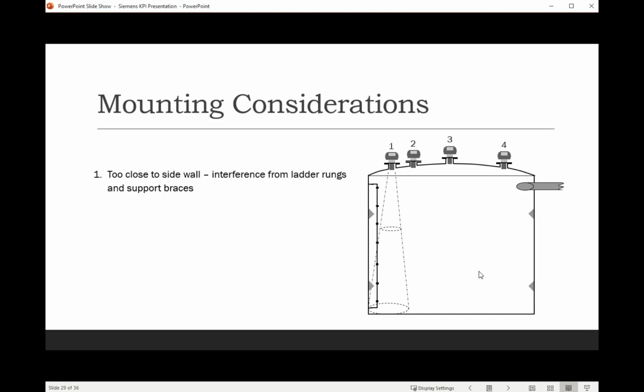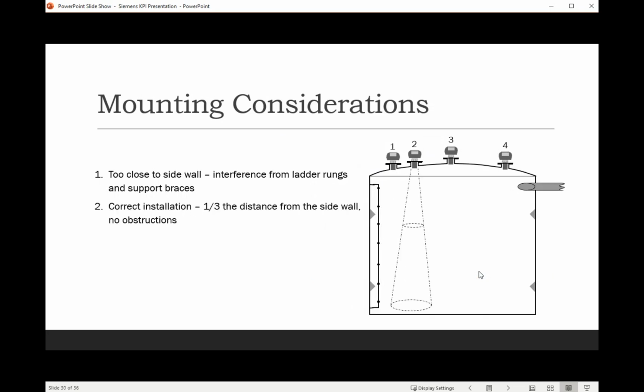If that does happen, we do have the ability to do some mapping out with auto false echo suppression, and we could possibly get that up and running. With number 2, though, installation number 2, 1/3 the distance from the sidewall, there's no obstructions. You should have no issues with getting an accurate reading and a solid signal strength coming back to the transducer itself.